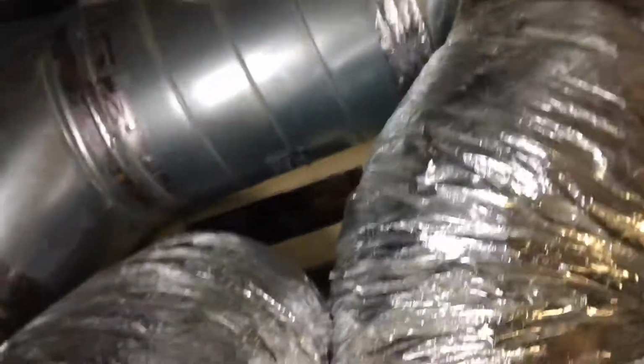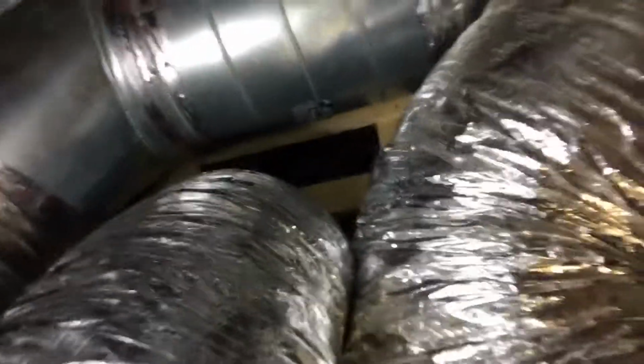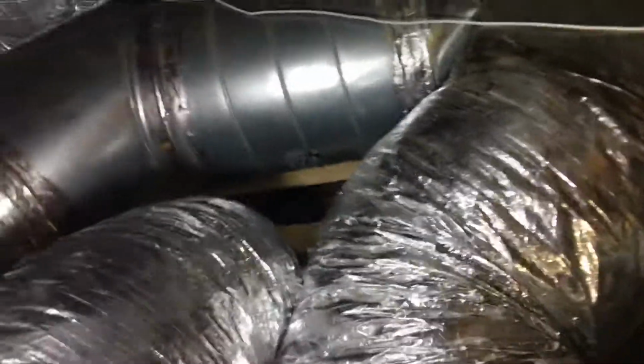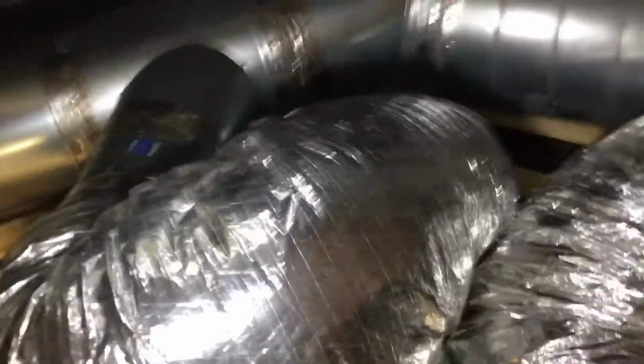Now the ductwork is getting so cold, the ground is all wet because they never insulated that, but it never worked right, so it never really got cold unless the filter got restricted and the evaporator turned into a block of ice. But now I'm making lots of condensation on this metal ductwork up here, so I'm fixing one problem and creating another that was never addressed because it was never insulated.